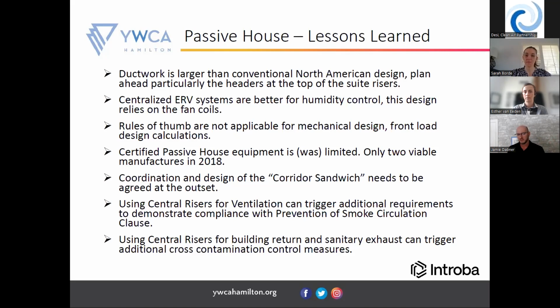If we were to do the design again, we probably would centralize humidity control to the ERV, as opposed to letting each fan coil pick up humidity control. It would probably make it simpler, and it would also maybe take some insulation out of the risers and make them smaller.